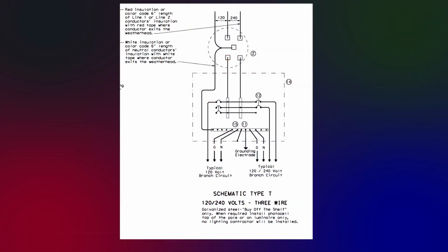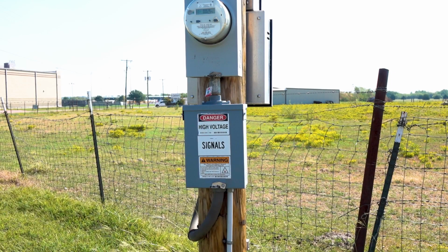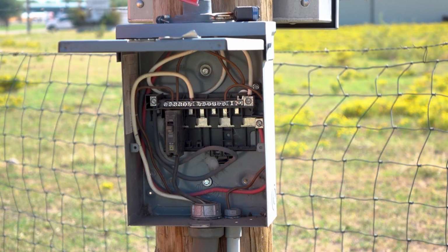A Type T electrical service uses a very basic electrical enclosure. Unlike TxDOT's custom-built Type A electrical service, the Type T electrical service uses a 120-240-volt off-the-shelf galvanized load center. A Type T service has 6 or fewer branch circuit breakers. Because there are 6 or fewer circuit breakers, the National Electric Code does not require it to have a main circuit breaker.